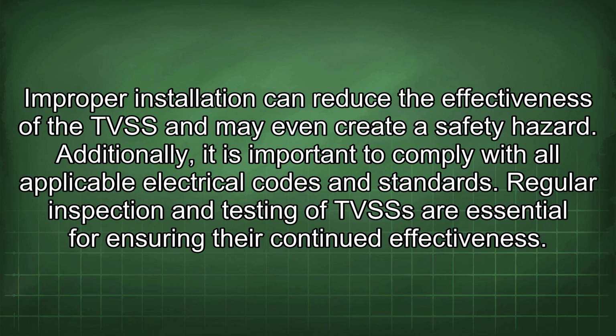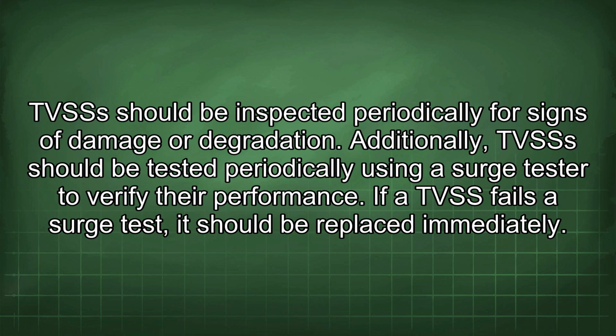Additionally, it is important to comply with all applicable electrical codes and standards. Regular inspection and testing of TVSSs are essential for ensuring their continued effectiveness. TVSSs should be inspected periodically for signs of damage or degradation. Additionally, TVSSs should be tested periodically using a surge tester to verify their performance. If a TVSS fails a surge test, it should be replaced immediately.